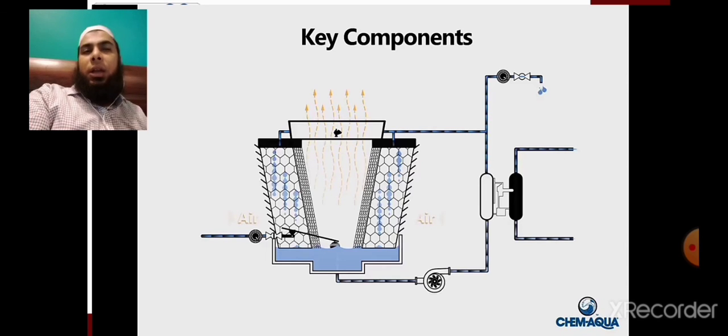That's why in industries we produce air conditioning at a very low cost, like 7 to 8 rupees per ton of cooling, whereas in your normal air cooled circuit like a split AC, the unit cost becomes 22 to 25 rupees per ton of chilling. I personally calculated this in one of my FYP projects.